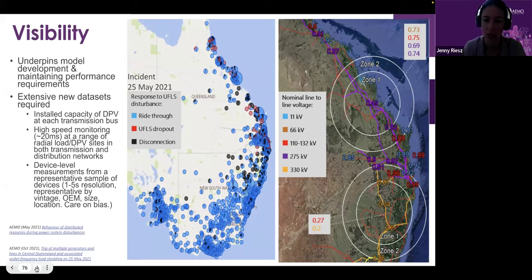The example I've shown here is a major incident that occurred on the 25th of May, 2021, in the southern part of Queensland. You can see the red and black dots in the graph about halfway up the coast of Australia. We had multiple explosions at some coal-fired power stations that led to voltage dips on the grid. On the right are the minimum per-unit voltages recorded across different levels of distribution and transmission, and in the bubbles on the left, the amount of PV that responded in different ways, with blue systems riding through, which is the desired behavior, and black systems disconnecting, which is undesired.